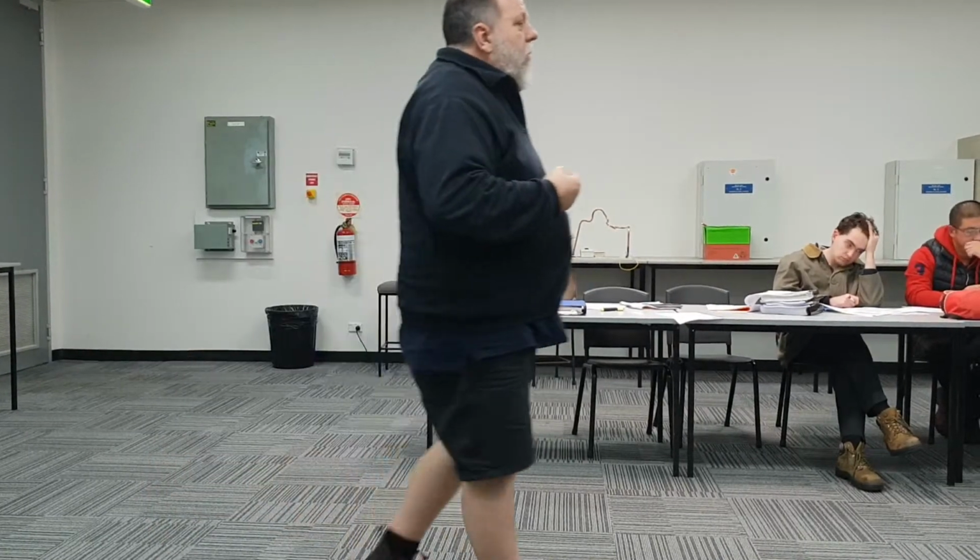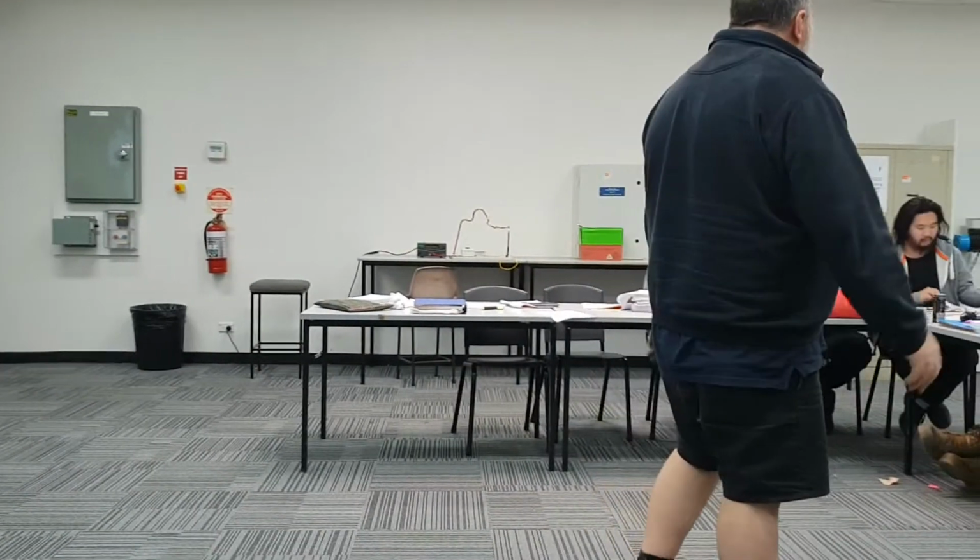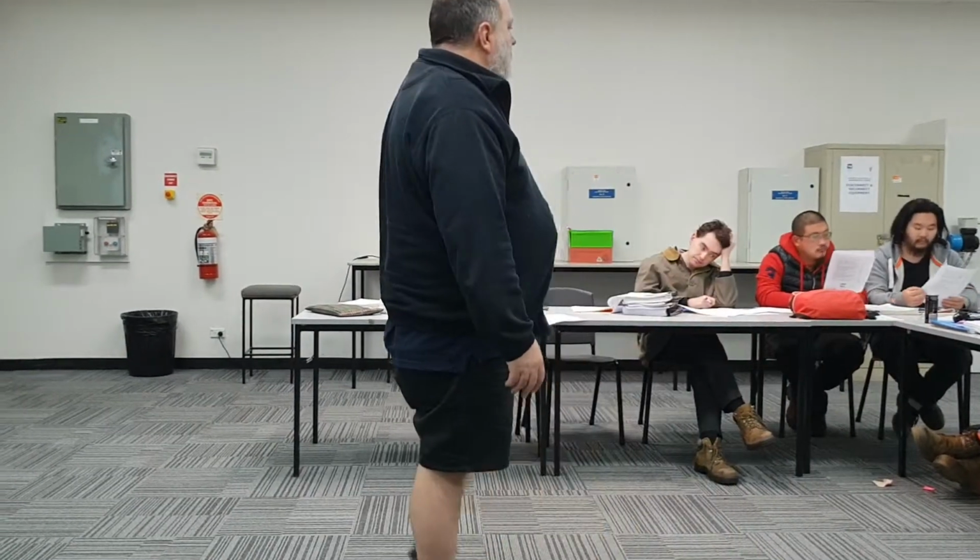So what happens is we get our units, we divide it by 3 across the 3 phases. Once we've done that, everything that we do inside that unit is times 6. So if I have, for example, in the lighting, what does it say for the lighting in column 3? 6 amps. Let's go to the one next to it. What does that say? 5 amps plus 0.25 amps per living unit.